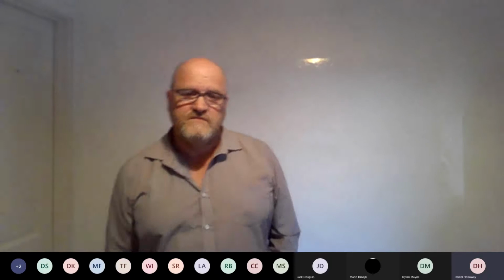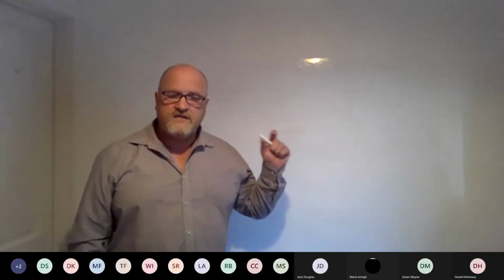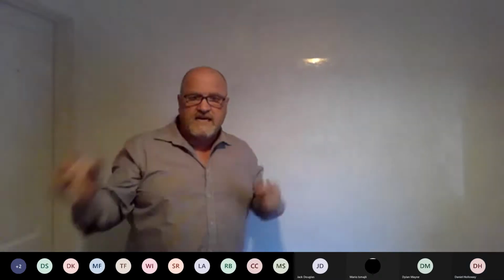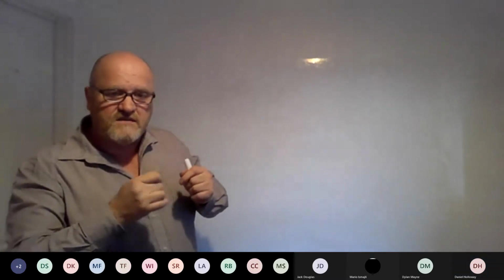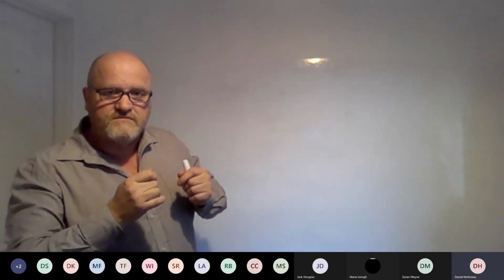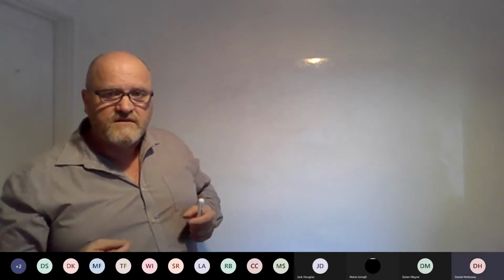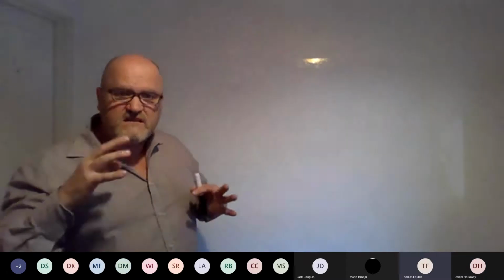That's insulation resistance. When you do your continuity test, you go from the switch to the lamp, connected together at the board. And you test at the lamp between the switch and the earth, the R1+R2 reading. Yeah, it's got to be below 0.6, isn't it? But that's because you've only got about a metre, haven't you?